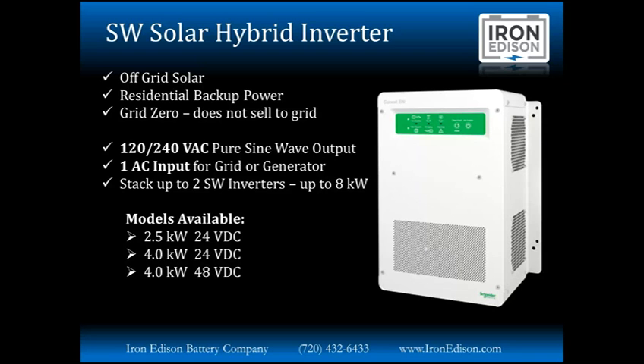So if you're grid interactive or connected to the grid, you can have the grid power come in to supplement your battery and solar. Or in an off-grid situation, you can use a backup generator. You can stack up to 2 of the SW inverters, giving you up to 8 kilowatts of power output in the inverter stack. And they have models in both 24 and 48 volts, 2.5 kilowatt output, as well as 4 kilowatt.